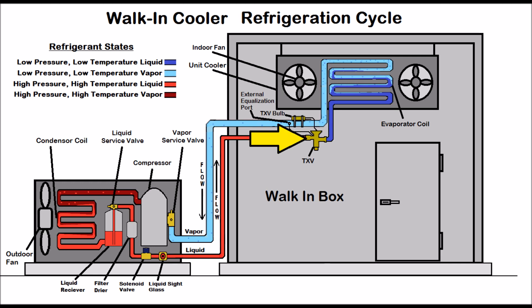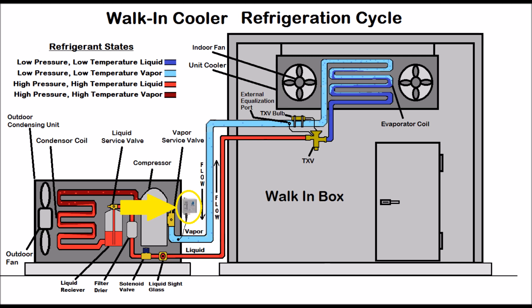The thermostatic expansion valve reads the superheat and tries to maintain it. In a walk-in box you're looking for about six to eight degrees of superheat once the temperature inside is lower. The superheated low pressure low temperature vapor refrigerant leaves the walk-in box and heads back to the outdoor unit. You may also have a low pressure control mounted on the suction line before it goes to the compressor. Then the low pressure low temperature vapor heads back into the compressor and the cycle starts all over.